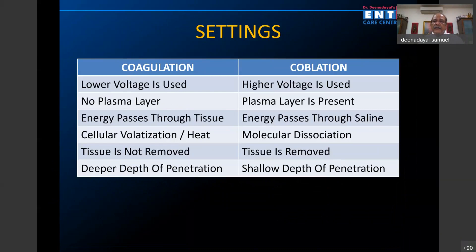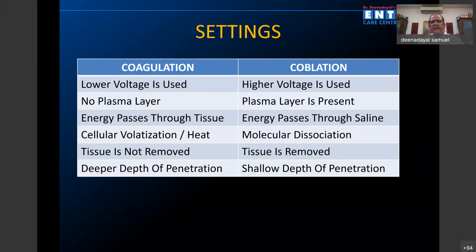In terms of coagulation versus Coblation: in Coblation, high voltage is used; in coagulation, it is low. In coagulation, there is no plasma layer, whereas in Coblation there is. Coagulation does not always require saline, but Coblation requires saline as an absolute necessity. In coagulation, no tissue is removed, whereas in Coblation tissue is removed. The coagulation pedal has a deeper depth of penetration, and Coblation has a shallow depth. Use coagulation when controlling a bleeder, though small bleeders can be controlled beautifully even by Coblation. Use as minimum coagulation as possible.